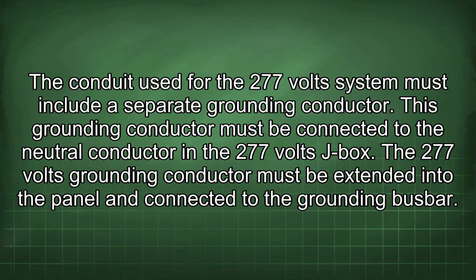The conduit used for the 277 volt system must include a separate grounding conductor. This grounding conductor must be connected to the neutral conductor in the 277 volt J-box. The 277 volt grounding conductor must be extended into the panel and connected to the grounding busbar.